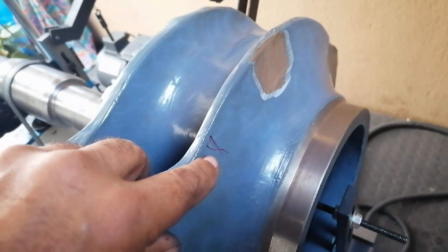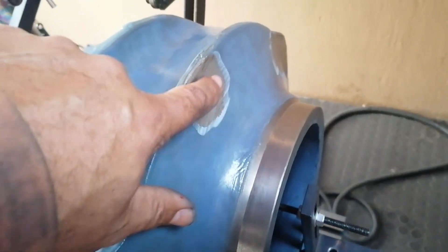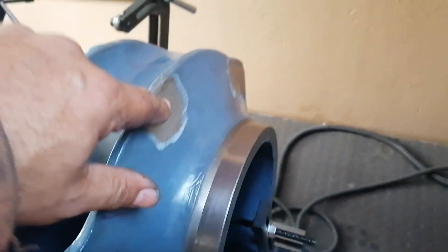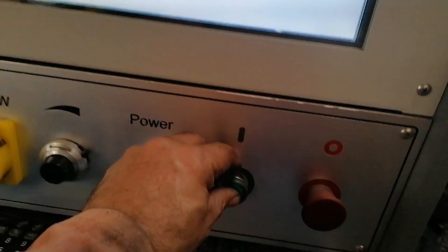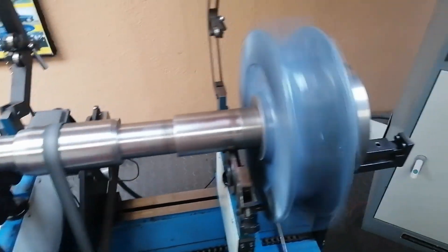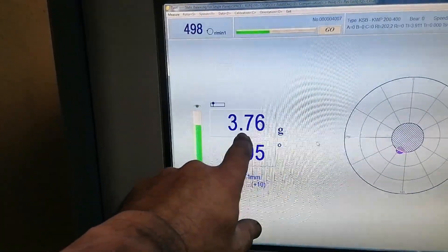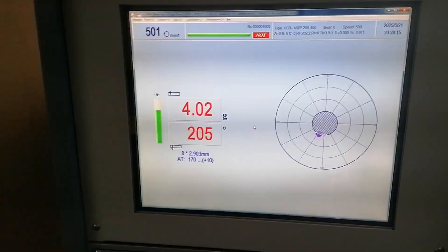This time I decided to take some more off there to minimize the amount to take off, so I'll see what effect this has. If it's bringing it down, I think I'll work on this spot again instead of having lots of different spots all over. She's going again - she's down to 4 grams, around 3 to 4 grams. I must work another spot.